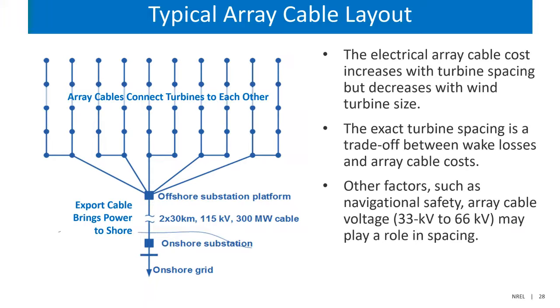Currently, array voltages at most projects were built at 33 kilovolts, or 33,000 volts between the array cables, but almost all projects are moving now to 66 kilovolts, or 66,000 volts. That helps with spacing, helps connect larger turbines, and lowers cost because you need less copper as the voltage goes up.